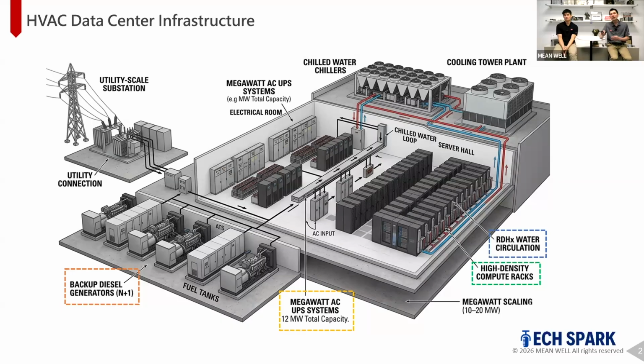You also see the AC UPS. What it does is provide backup that can last about 5 minutes, for the time it takes the generator to start up, because the generator takes some time to start. So when there's a power outage, the AC UPS kicks in and the generator starts up to do the backup. That's why you have the AC UPS system there.